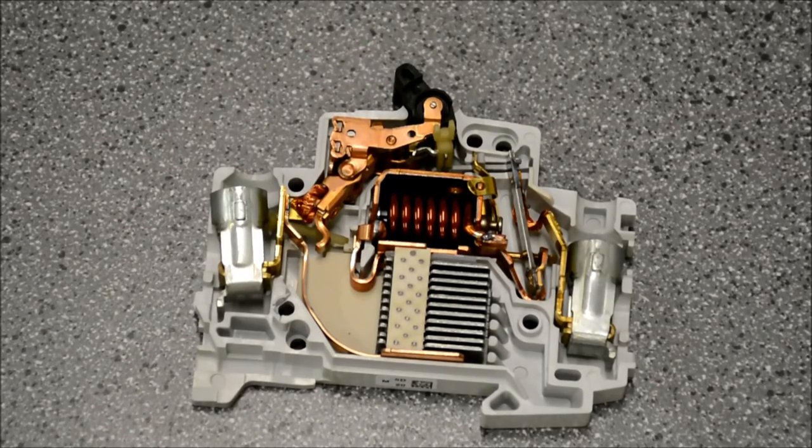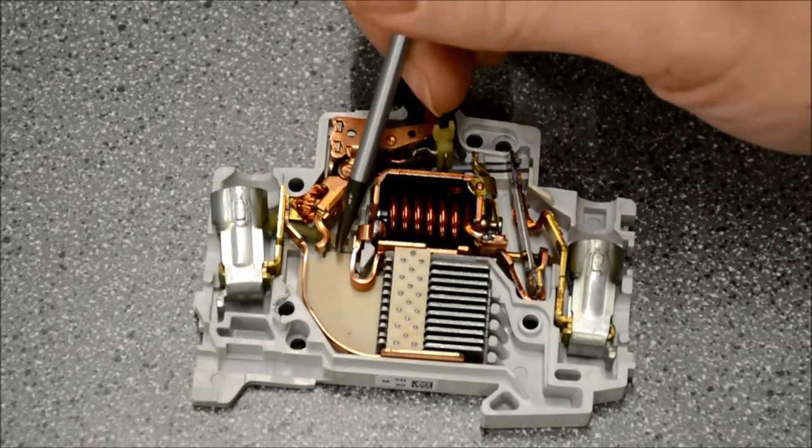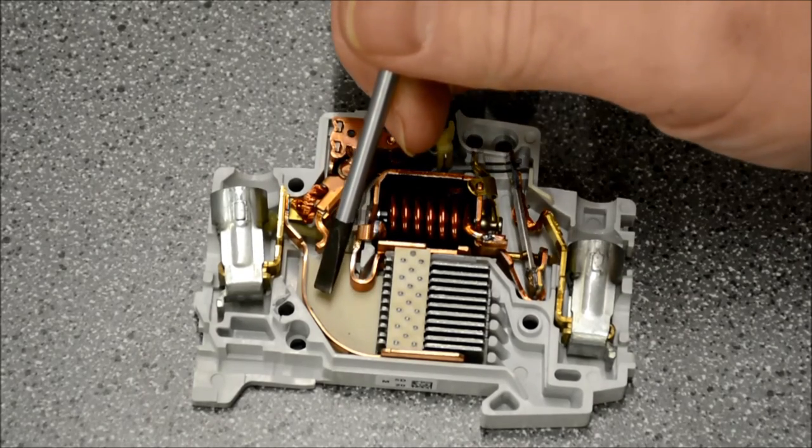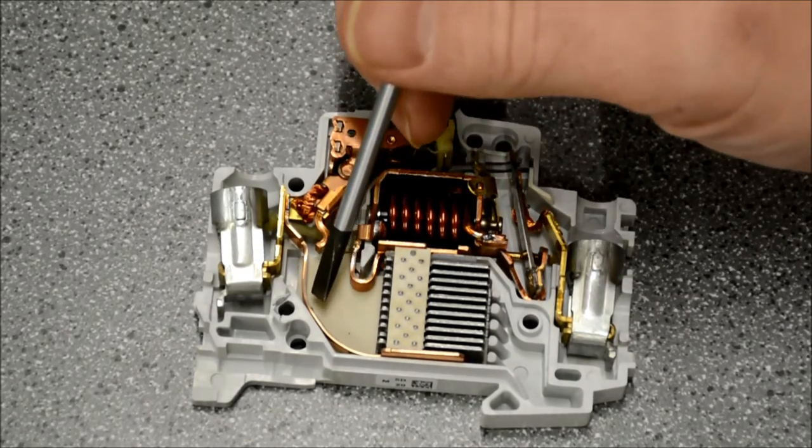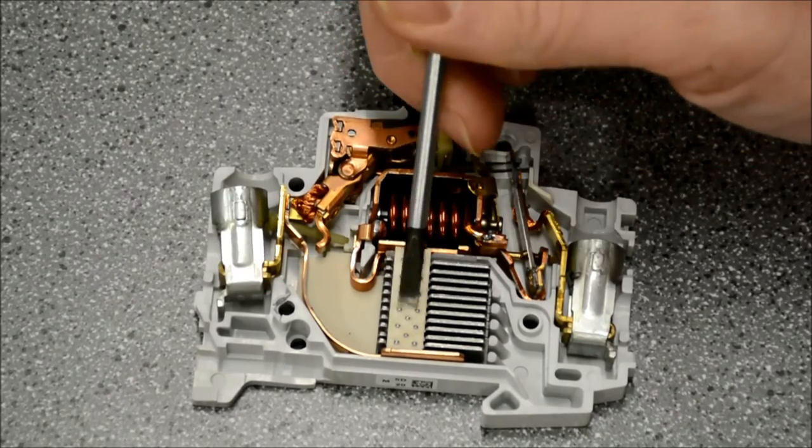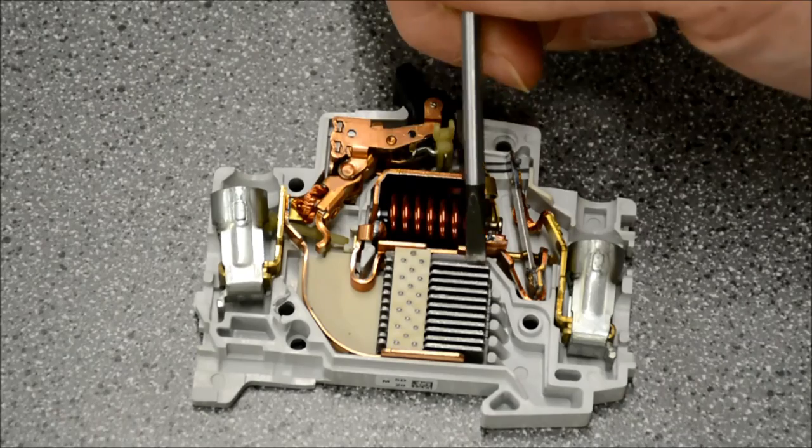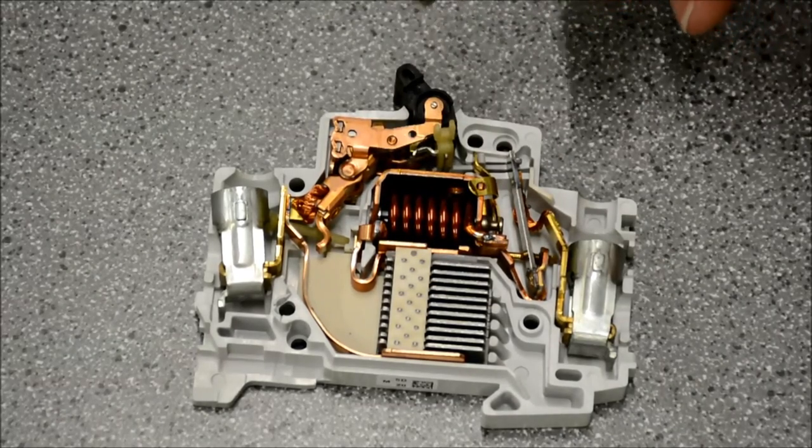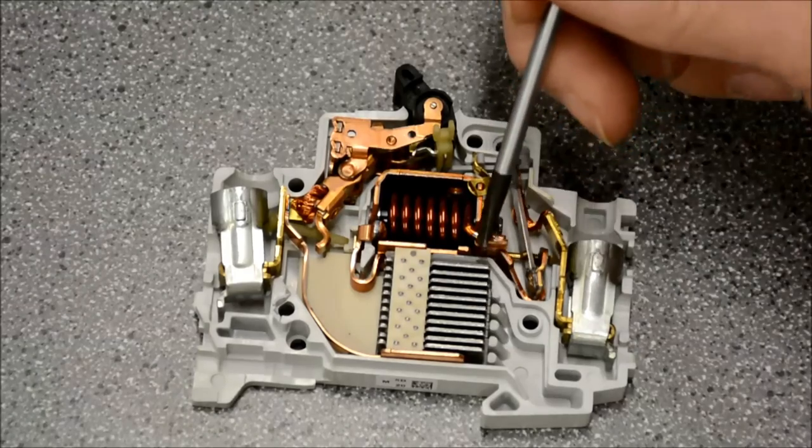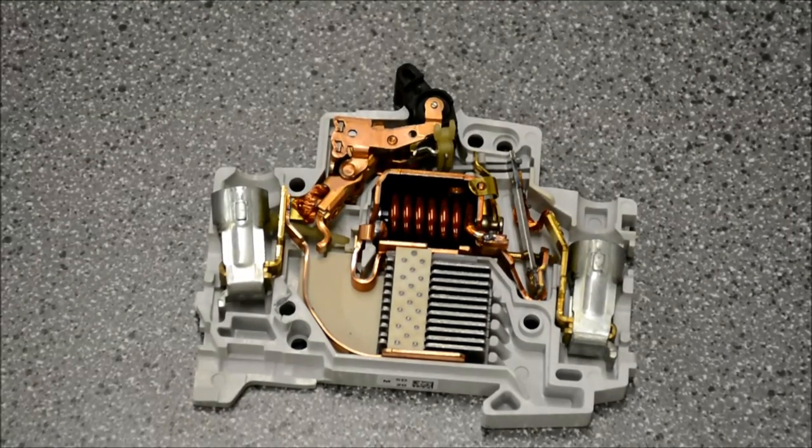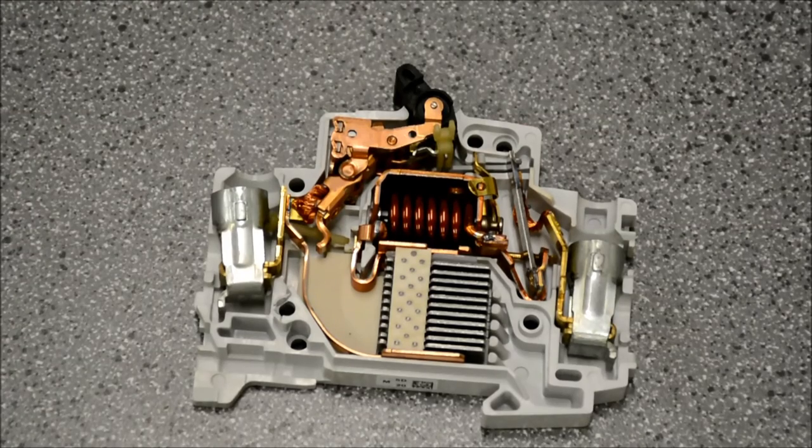So as the circuit breaker opens, that large arc travels down and it is funneled in this direction by this metal strip, and then it is directed through these arc chutes. These arc chutes serve to dissipate that arc. It takes one large arc and breaks it into several smaller arcs, and it also acts as a heat sink to absorb the heat and help the circuit breaker dissipate it effectively.